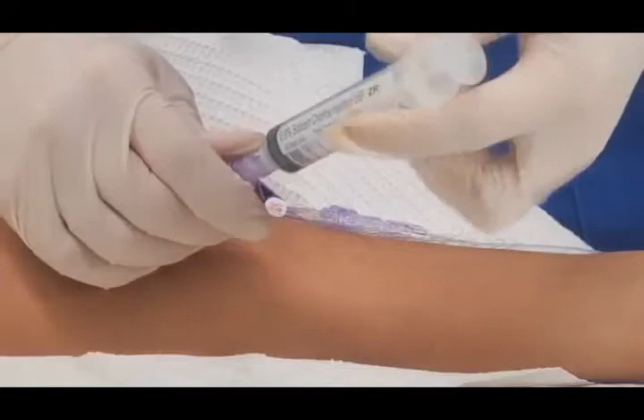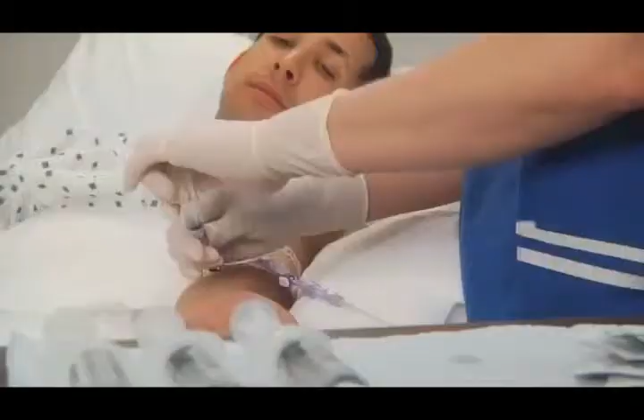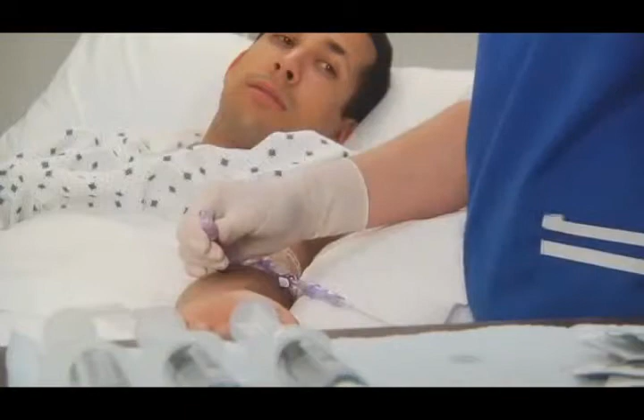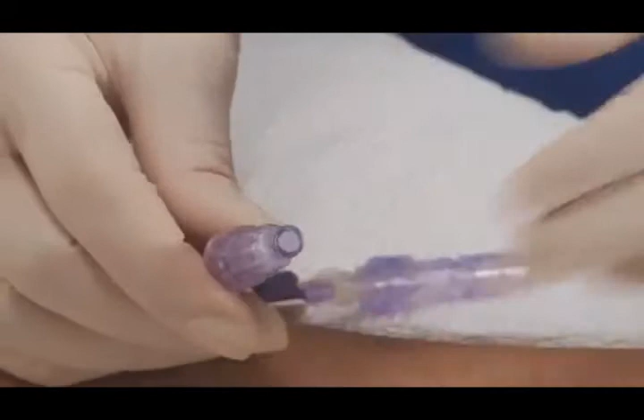The clinician is preparing to disconnect the final flush syringe after completing the flush procedure. She visually confirms that the fluid path has been appropriately cleared and then disconnects the syringe. Clamping the IV line is not necessary with the Caresite Luer access device. However, individual healthcare facility protocols may require IV lines to be clamped when not in use.